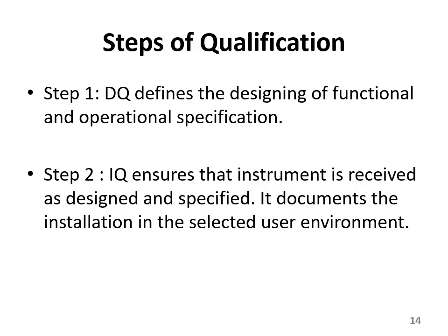Definitely you got your machine, or you got your product, and now you want to install your machine or your equipment in your environment. Now it is very important, if you are installing an HPLC in Oxford and in Lahore, there is a hell of a difference between the temperature of the two areas.